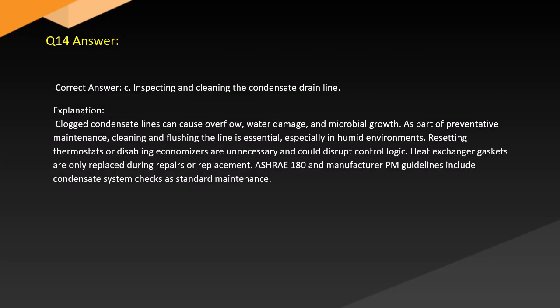Answer. Correct answer: C. Inspecting and cleaning the condensate drain line. Explanation. Clogged condensate lines can cause overflow, water damage, and microbial growth. As part of preventative maintenance, cleaning and flushing the line is essential, especially in humid environments.